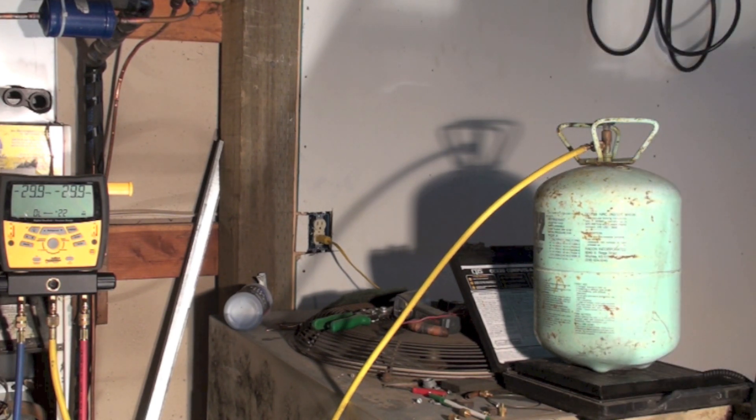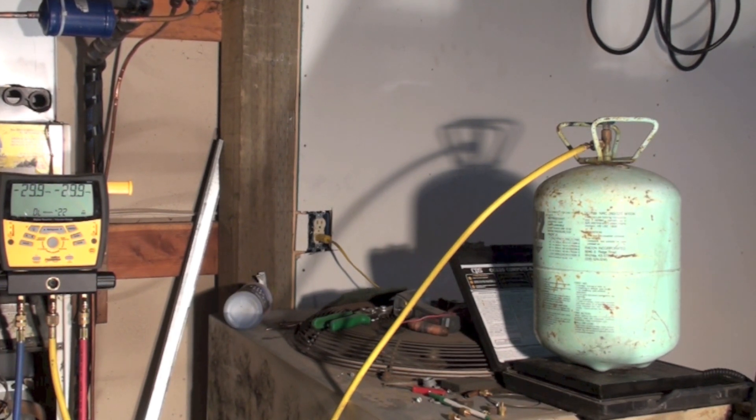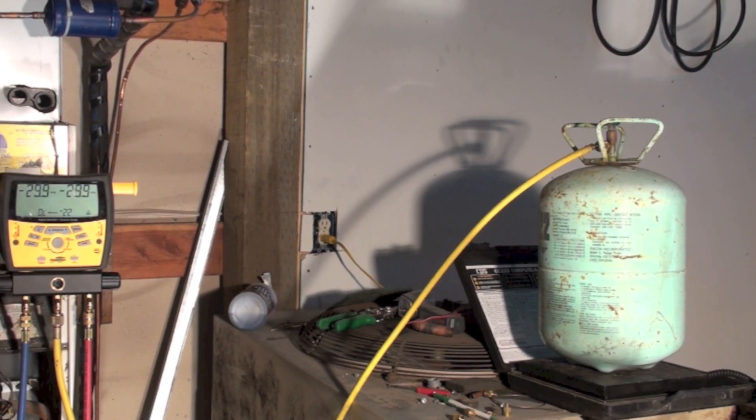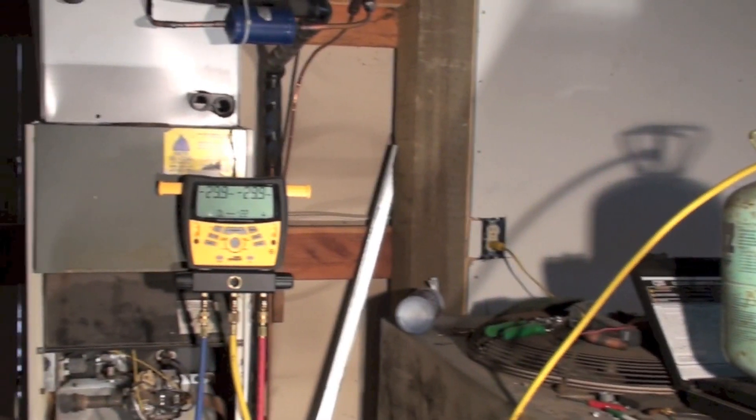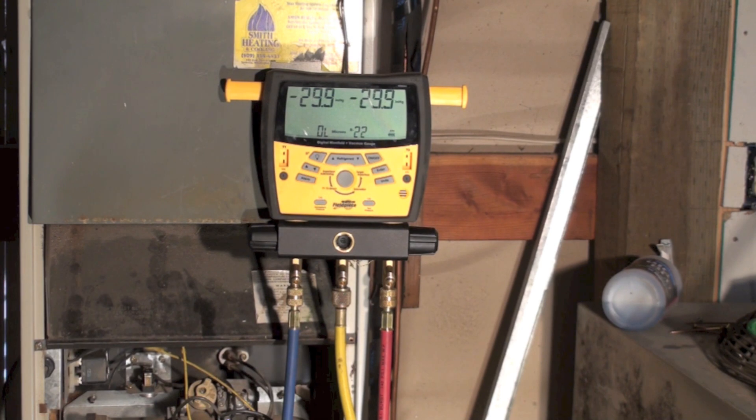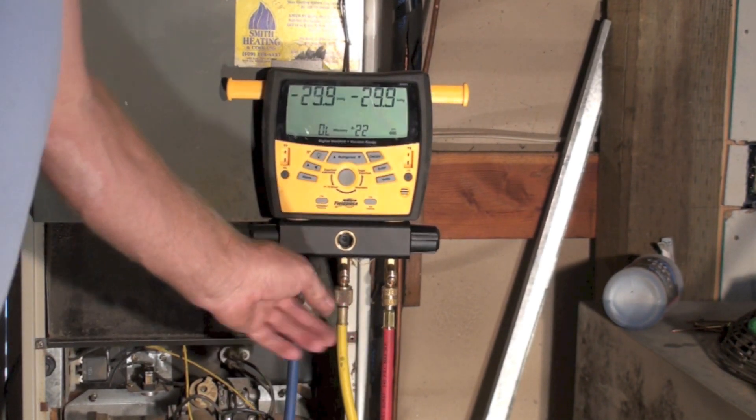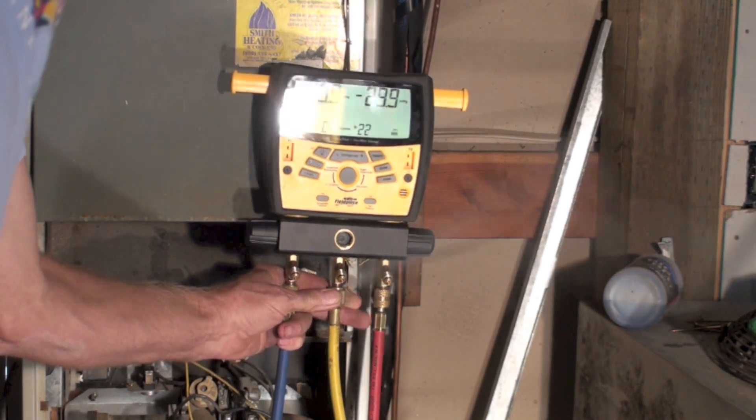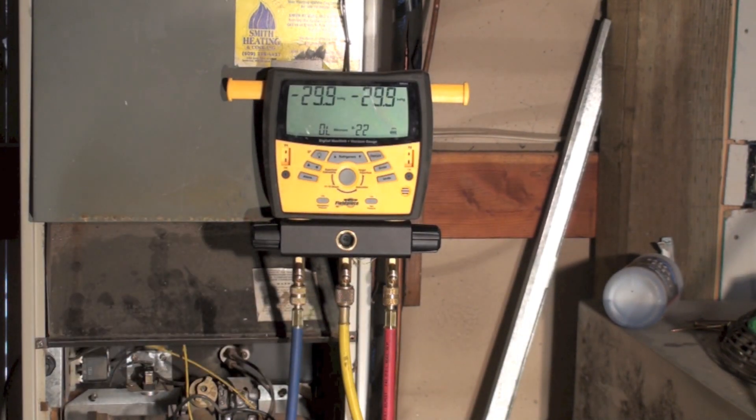Now, I put pressure on the hose. So now I'm going to go over to the gauge set. Where the yellow hose comes in, I'm going to bleed. That's plenty right there. Just a half second or so. And it has bled any air in the system out.